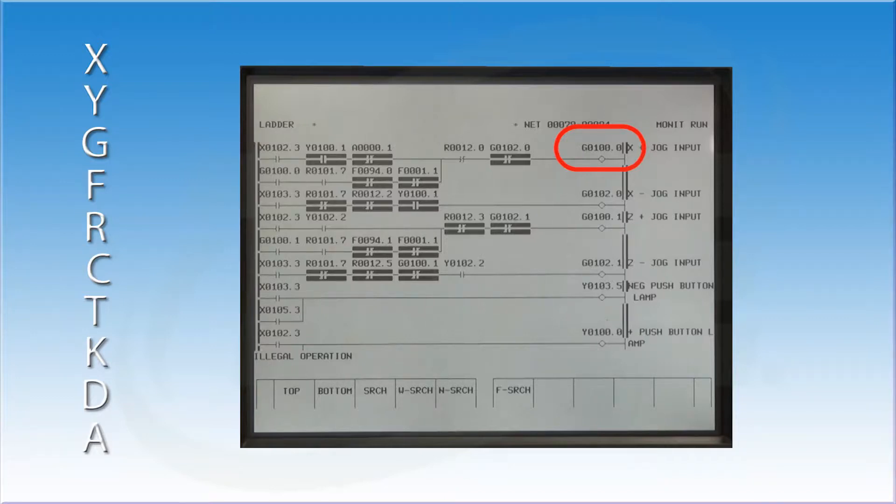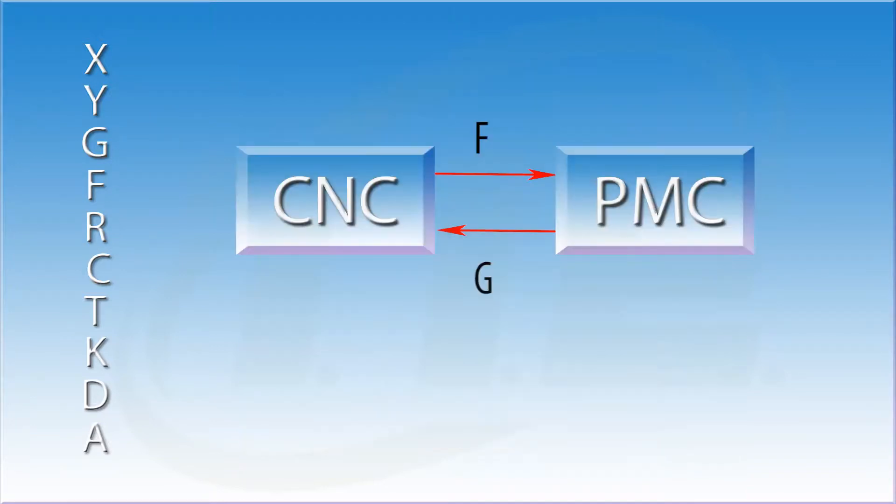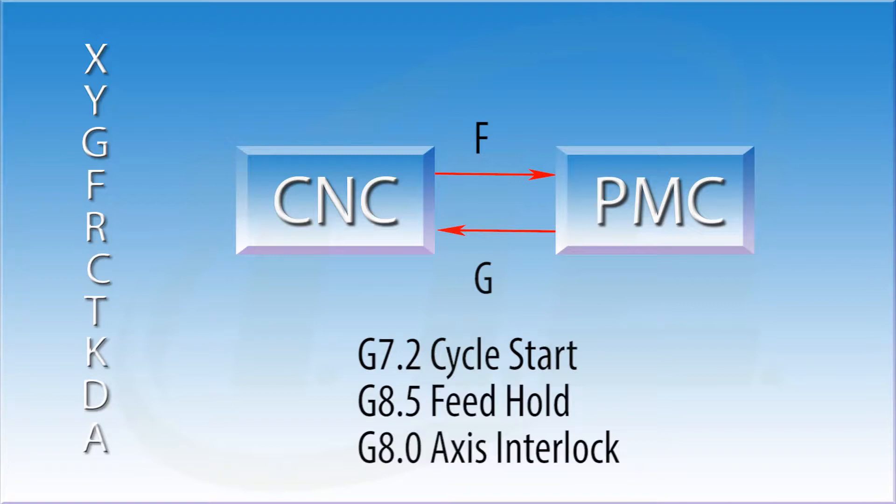Go into the ladder. Look up address G100.0. Look to see if it is going high. If it is not, the axis was never told to move. The CNC is doing what it thinks it's supposed to be doing, holding still. The secret to troubleshooting a lot of machine tool problems lies with understanding the F and G addresses. Once you understand how they work, the amount of time it takes to solve a large number of machine problems can be cut in half.